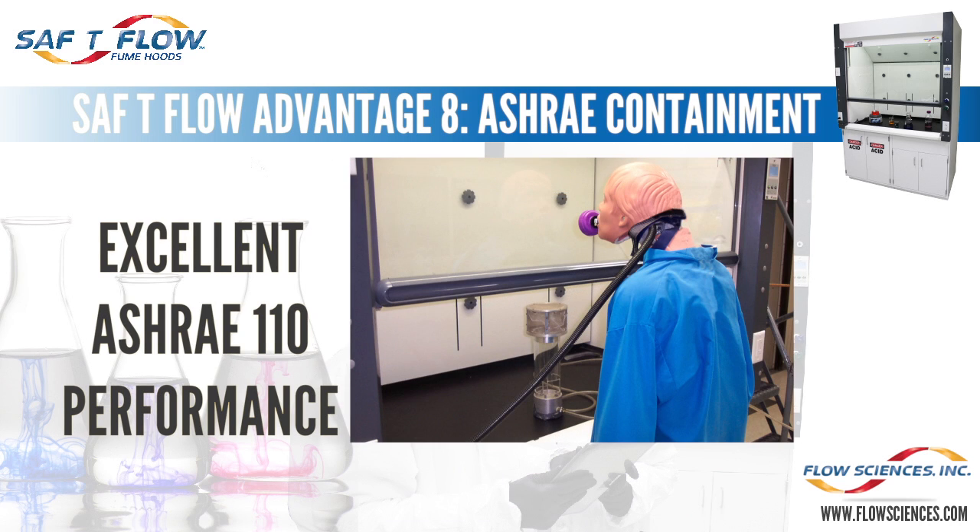Advantage eight: the Saf T Flow fume hood is third-party tested per ASHRAE 110-1995 at containment levels of one-tenth of the AIHA Z9.5 standard of 0.05 parts per million. Flow Sciences has tested the Saf T Flow fume hood at 100 feet per minute — the standard accepted industry-wide — but also at lower velocities of 80 and 60 feet per minute. The third-party containment results show actually indistinguishable containment across those three face velocity levels. 60 feet per minute appears to be a velocity this fume hood can accommodate without any infringement on laboratory safety.